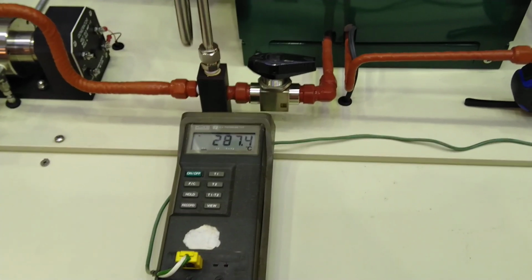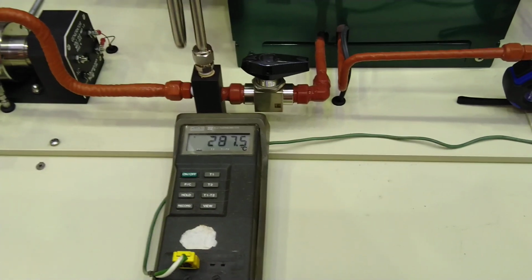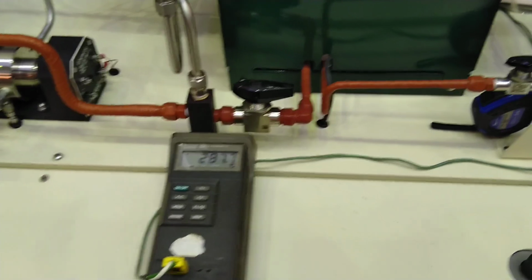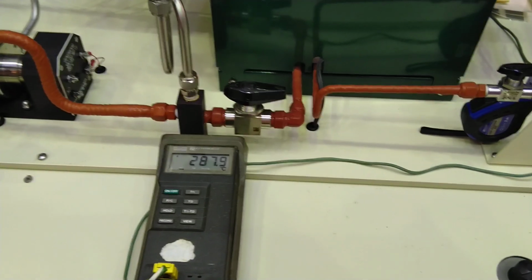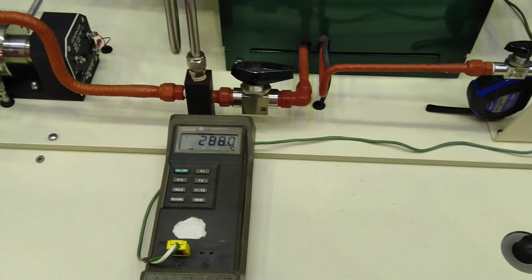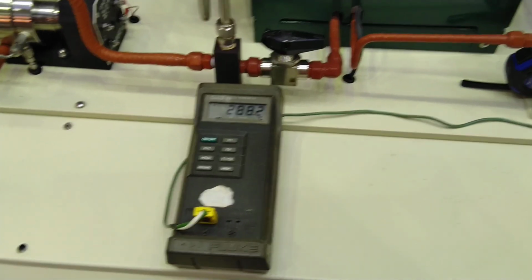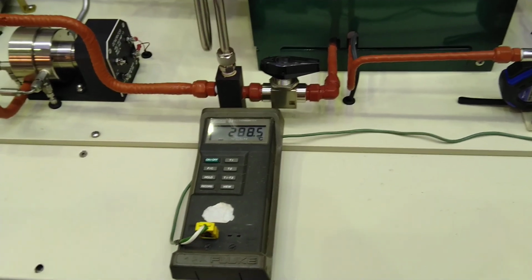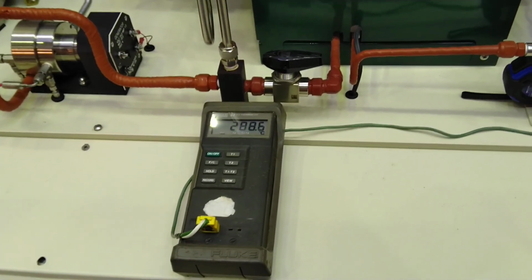And from this flue gas temperature outlet, then you could do the energy balance from the flue gas side. After you've done the mass balance and you have your air to fuel ratio, and then you have the amount of flue gas leaving from the system. And of course the room temperature here is 23 degrees Celsius. This you also need as an input or reference point.